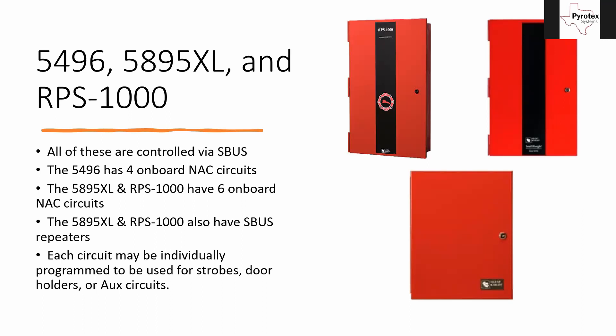These are three different Silent Knight and Farenhyt models that more or less work the same, so I grouped them together. They're all controlled via SBUS — the four-wire data circuit — and it can be T-tapped. The 5496 has four onboard NAC circuits and no onboard auxiliary power; if you need aux power, one of the NAC circuits has to be converted. Each circuit can be configured to be anything you want — a strobe circuit, door holder, auxiliary power, whether that aux power needs to be resettable or non-resettable, et cetera.